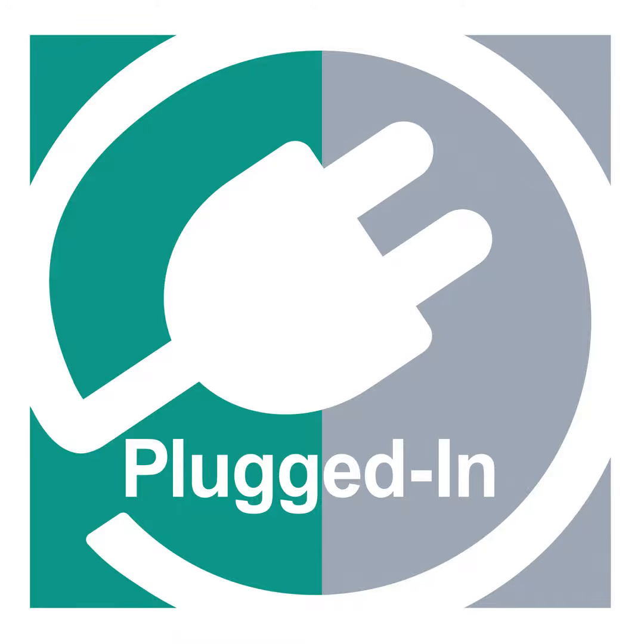Oh, so it's a different power supply that needs to be utilized compared to what standard factory automation does. Yeah, so factories tend to standardize on 24 volt. And what the voltage boost technology does is it'll take that 24 volts and actually bump it up to 48 volts to the devices that it's providing power to. So with a standard factory 24 volt power source, you can meet those 802.3 PoE specifications for power.